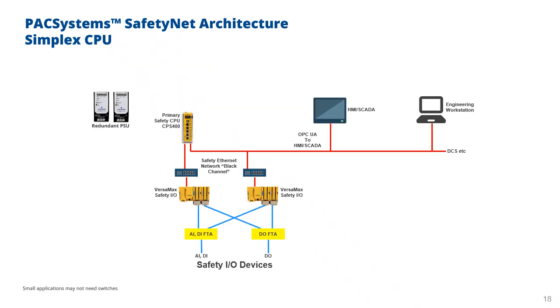So let's take a look at some architectures. This is a probable minimal system. We have a simplex safety CPU. We've got the black channel network, and we've got 2 sets of Versamax safety I/O with the required field terminal assemblies going down to the safety I/O devices. Note on this one, we've only got a single link between the I/O and the CPU. The CPU has 2 ports, so effectively those switches may not be required. So you could do a very small low-cost safety system with a fairly small set of components.